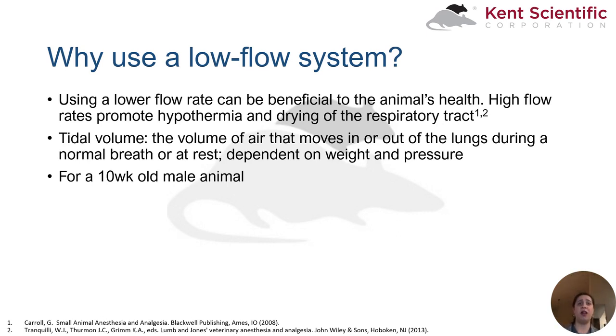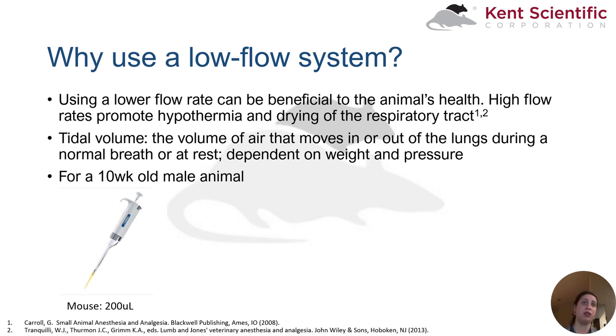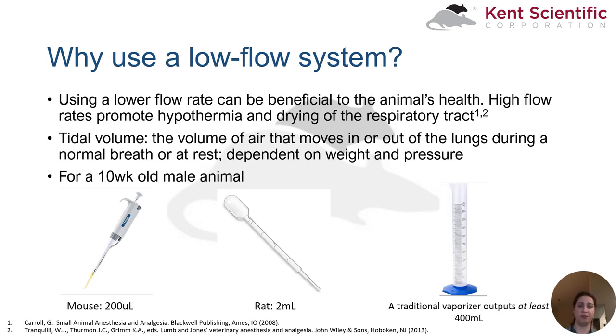Tidal volume — the volume of air that an animal breathes during a normal inhalation-exhalation cycle — is much smaller in laboratory rodents. For a 10-week-old male animal, mice generally have around a 200 microliter tidal volume, something you can easily measure with a micropipette. Rats have a tidal volume of around 2 milliliters, measurable with a transfer pipette. Traditional vaporizers, by contrast, export hundreds of milliliters of gas — measurable with a graduated cylinder. Imagine being a mouse with a micropipette-sized tidal volume having a graduated cylinder's worth of air flushed into your respiratory tract — this isn't necessarily good for the animal's respiratory system.